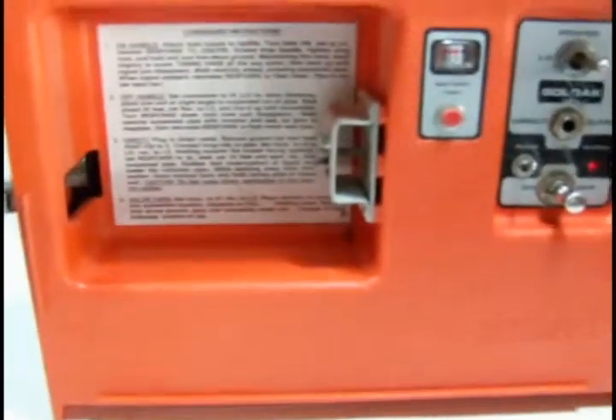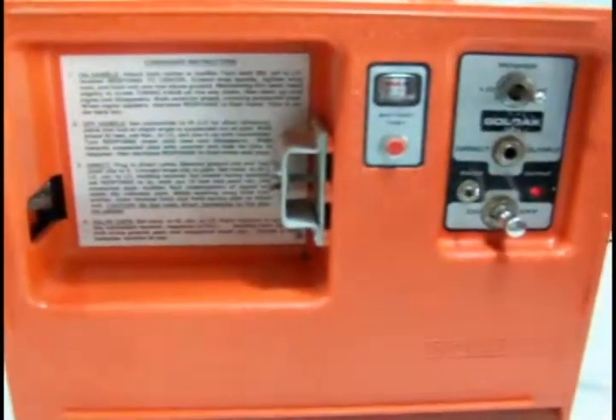There's a connection here for a handle. The handle is about a four-foot handle that slips inside here into the transmitter, and on the receiver end there's a hole to fit the other end of the handle. The transmitter and the receiver sit perpendicular to each other. So the transmitter transmits a signal perpendicular to the earth, and transmits the magnetic field running at 116 kHz down into the ground, and the receiver picks up the pipe or the cable as parallel to the ground.